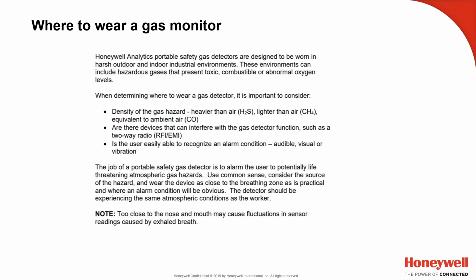You may want to take that reading, but then as you start to introduce ventilation, you're going to stir up that gas. So even if you're wearing it on your hip, typically it's going to be the same atmosphere that's a foot or two away from your nose and mouth, which would be considered the breathing zone. The other thing to consider is that if it's too close to the nose and mouth, and you download the data logs after using the detector, you might see the oxygen have a sawtooth curve, going up and down as you inhale and exhale, and it sees low oxygen. So the readings can be affected if it's too close to the breathing zone, ironically.